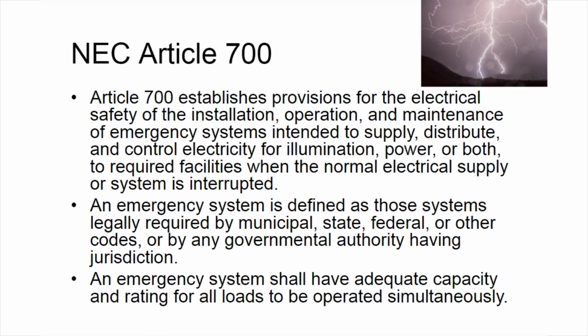The EPSS can serve optional loads as well as the code-required loads as long as certain criteria are met. And these criteria include selective load pickup, load shedding, and peak shaving. So basically, we have to ensure that the most critical loads, the life safety loads, are the default loads and are always on. It also allows for ground fault indication versus ground fault protection so that we don't have to trip out emergency power just because of the ground fault. Another mandate of Article 700 is that all emergency lighting be kept entirely independent from other systems, including raceways and barriers and switchboards. So a lot going on here, and you need to really dig deep into this code to understand how best to protect your system.